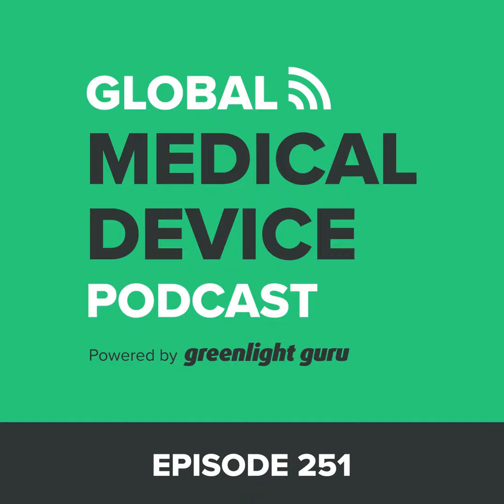Well, when I was at a company doing external defibrillators, they blew it out this way. It's like, you can't build it that way. So the designer laid it out in this CAD drawing. It's like, no. So we ended up creating part numbers in between, but using the same design drawing, because they had it on one picture. We're going to do this as 2 manufacturing jobs and do them differently, but using the same design drawing. So that's where that comes in and really helps you understand things. So when you talk about bill of material, you really need to understand it from the manufacturing side.